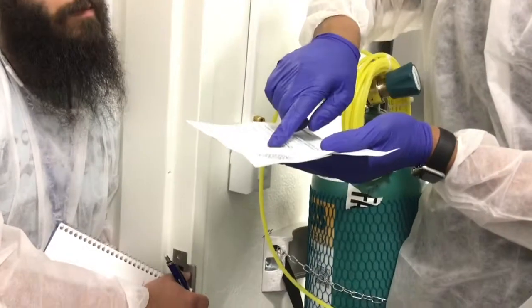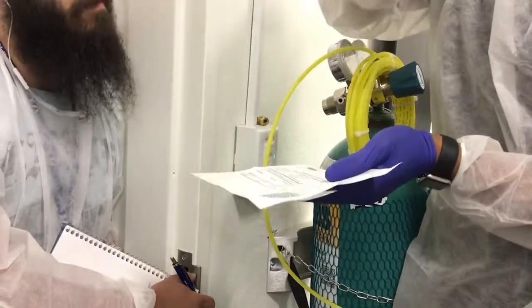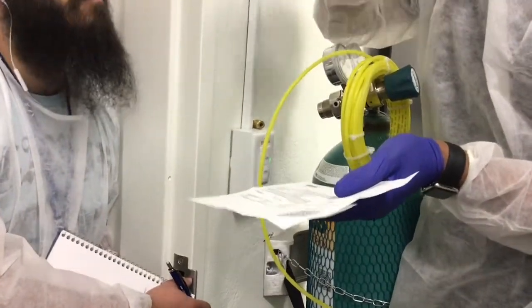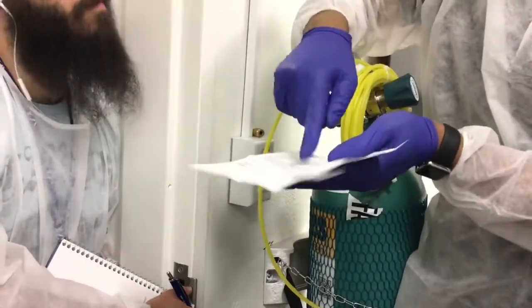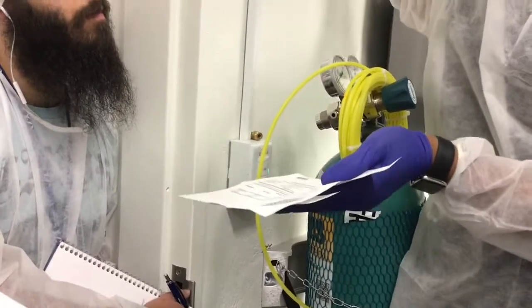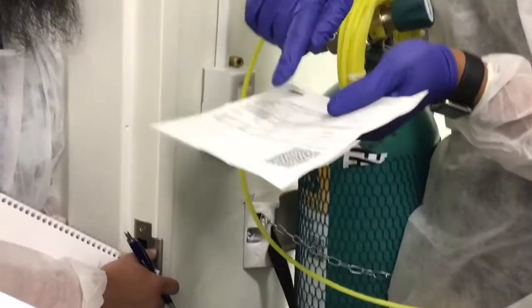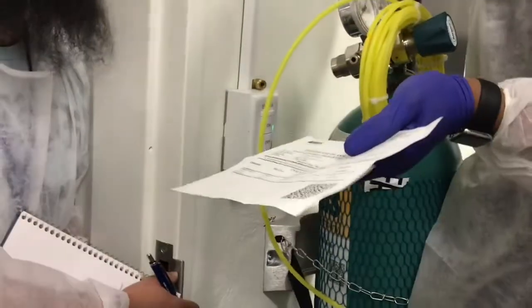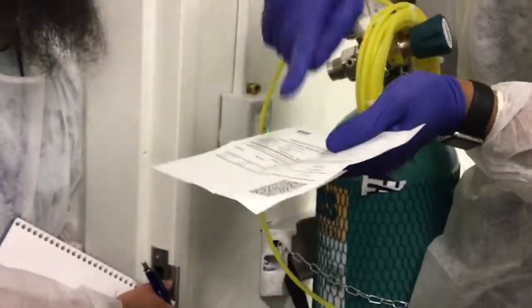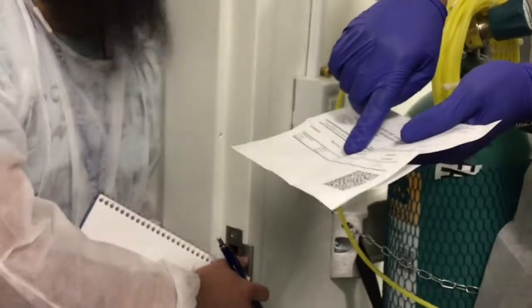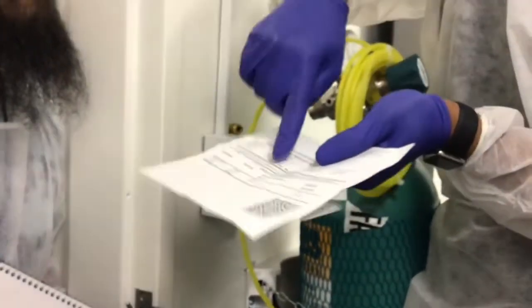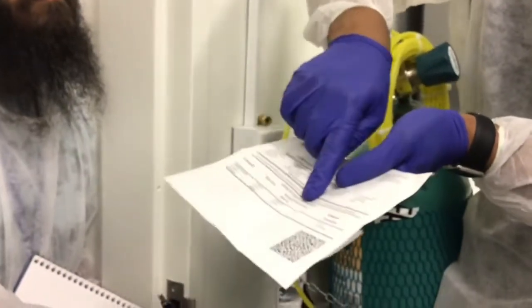It won't matter right now, because anytime you have a new gas tank, you just need to change this one time and calibrate. The software will record it and remember it, and that will be set as the default. So right now you don't have to worry, your default is already set since I calibrated already, and we will calibrate again. We won't have to change it. But if you get a new gas tank, don't use those default numbers. You get this paper and you go to the actual concentration.